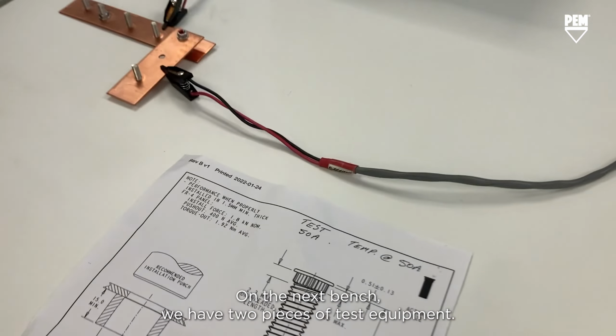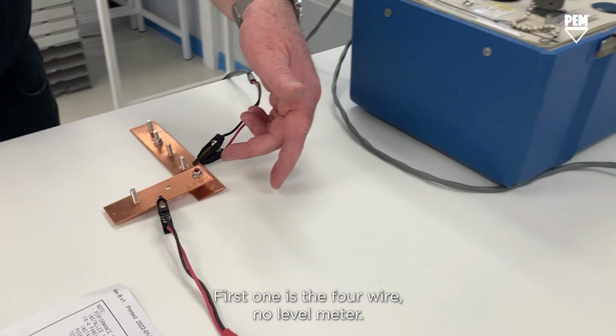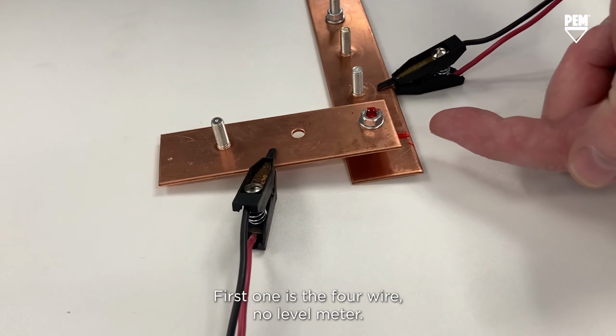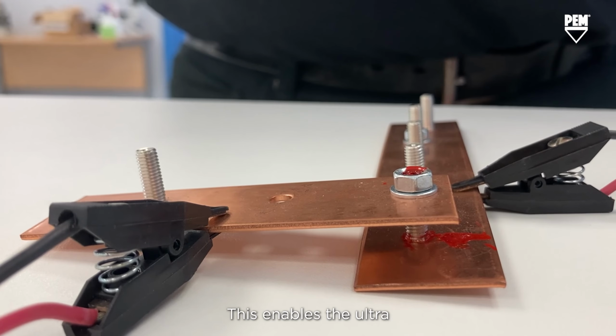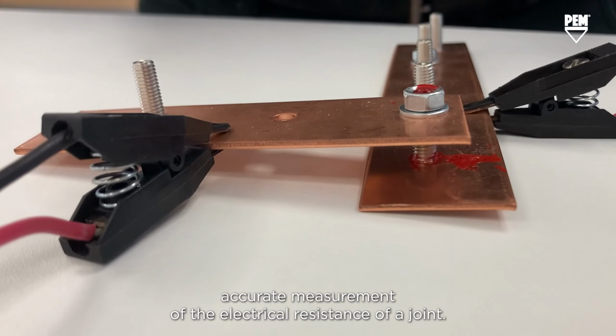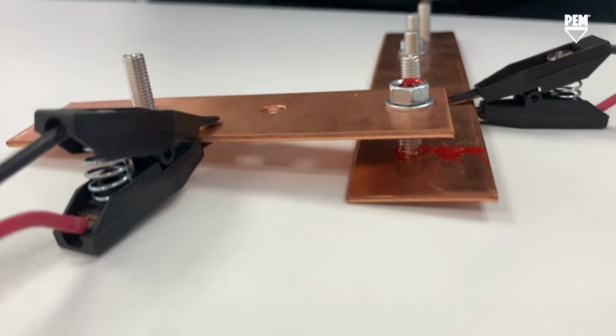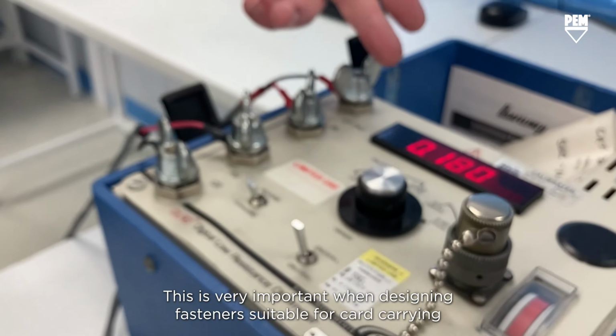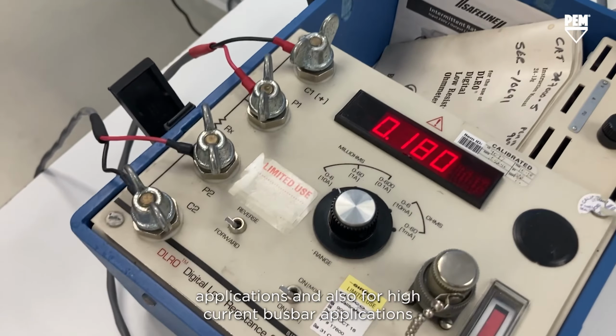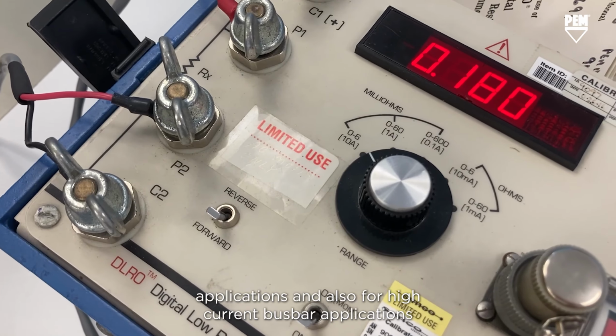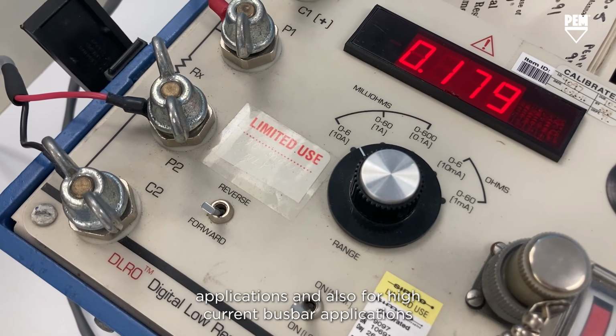On the next bench, we have two pieces of test equipment. First is the 4-wire low-level ohmmeter. This enables the ultra-accurate measurement of the electrical resistance of a joint. This is very important when designing fasteners suitable for current-carrying applications, and also for high current busbar applications.